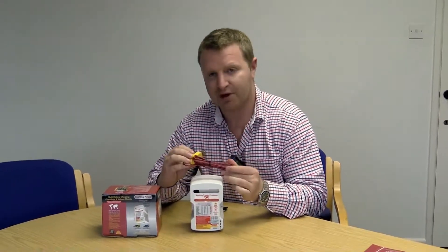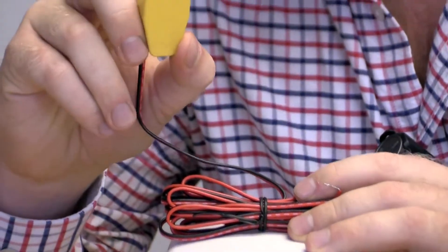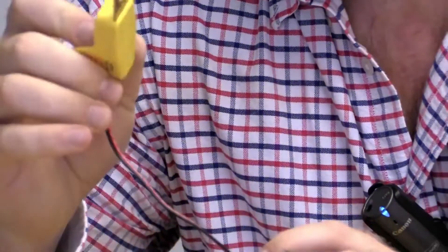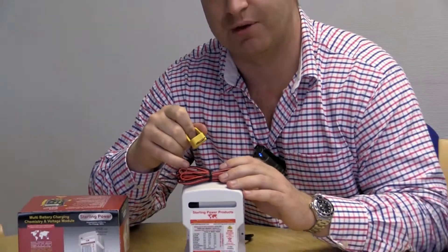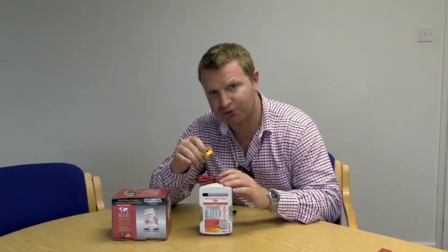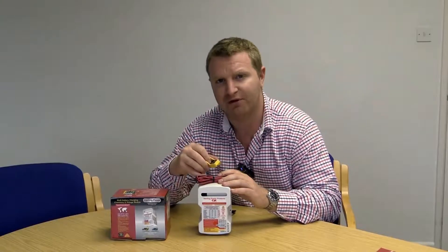Another feature of the battery chemistry module is it comes with a temperature sensor with 10 meters of cable. The positive and negative connect onto the circuit board of the BCM, and the yellow connector attaches to the negative terminal of the 12 or 24 volt output battery. The BCM will then compensate its output voltage for temperature: as temperature warms up, output voltage drops slightly; as temperature drops, output voltage increases to compensate.